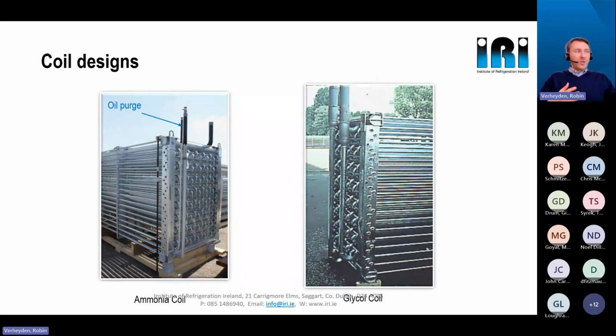So in general, we saw two different types of installation, internal and external melt. With external melt, we have both ammonia and a glycol solution. Here you will see the difference in the coil. A typical ammonia coil will have an oil purge, where a glycol coil will equally distribute the flow between different circuits.